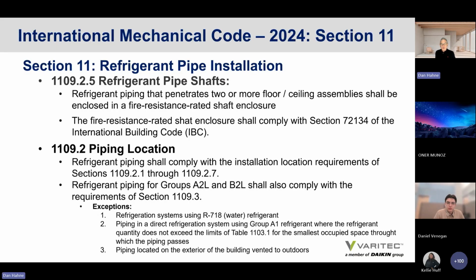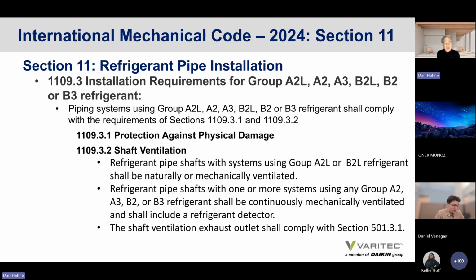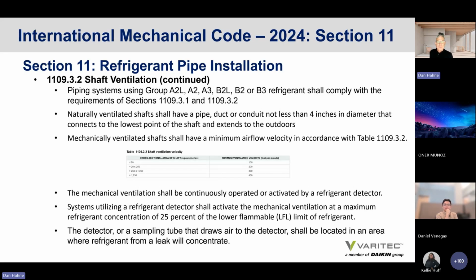It also gives direction on refrigerant pipe shafts. Refrigerant piping that penetrates 2 or more floor or ceiling level assemblies shall be enclosed in a fire resistance rated shaft enclosure. The fire resistance rating, there's a typo, that the enclosure shall comply with section 713.4 of the International Building Code. There's direction on location of pipes, and also in the use and design of A2L refrigerants, it gives shaft ventilation requirements that would be needed where you have refrigerant piping penetrating more than 2 levels. So be aware of that. That will now need to be incorporated into the architectural features of a building.